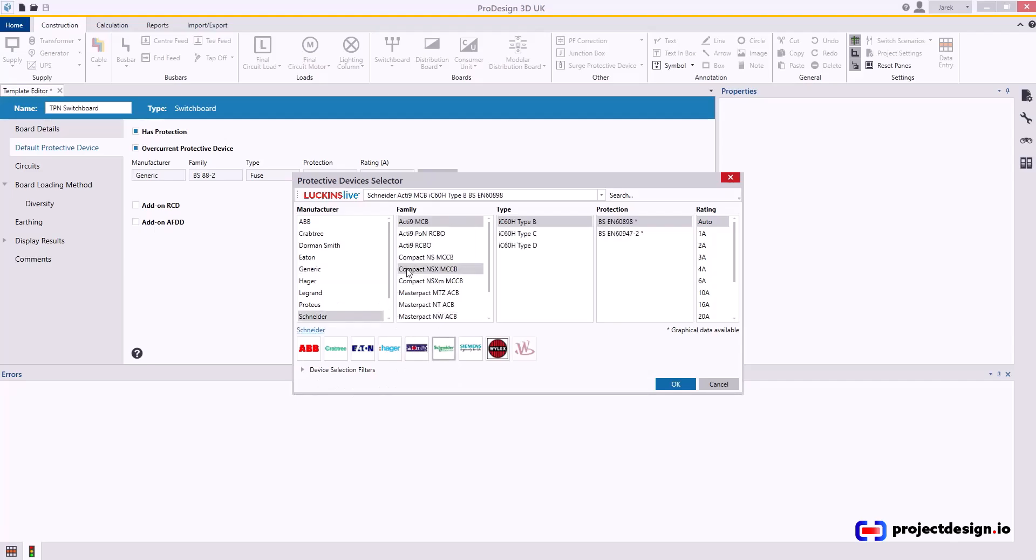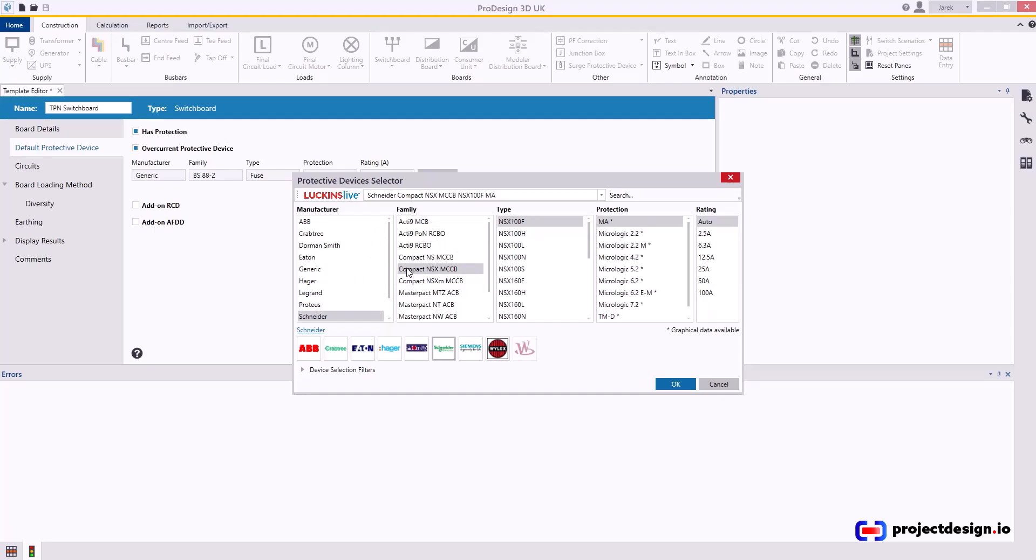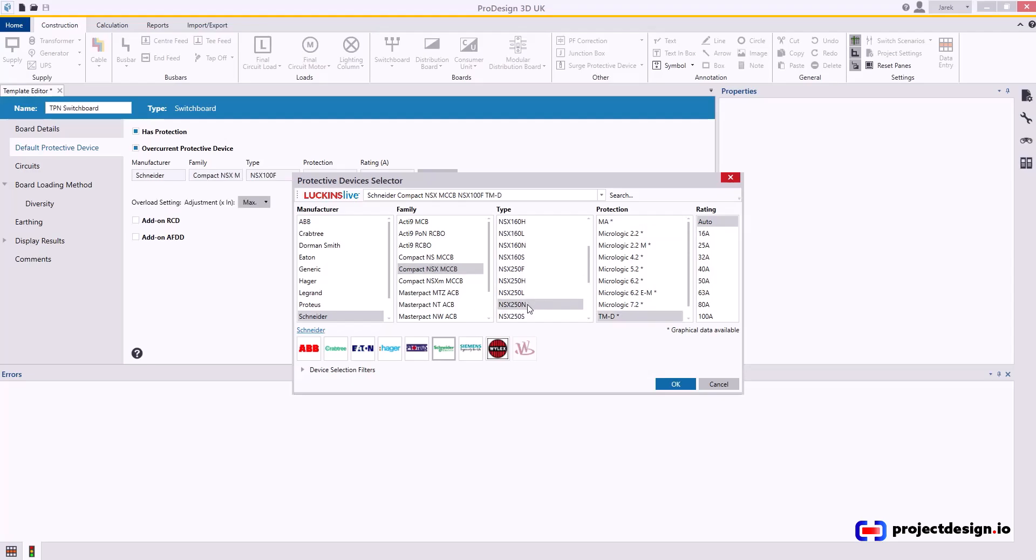Most typically I'm using NSX range devices. There is no typical size, but if I had to choose I would select either 250N, and N is 50k rated, or 400N. Let's go for 250N, 250 amps Type N which is 50k rated.